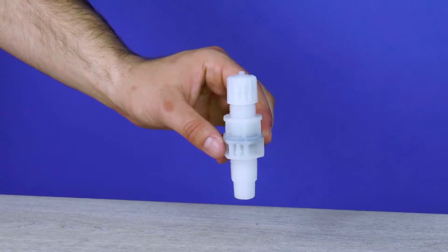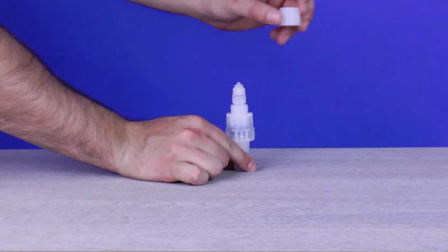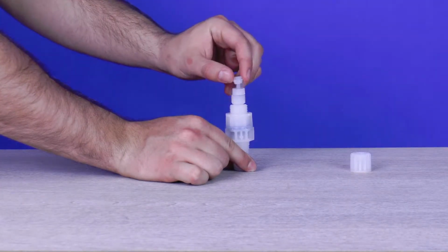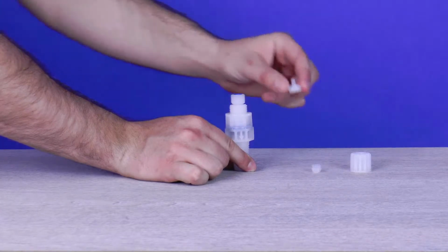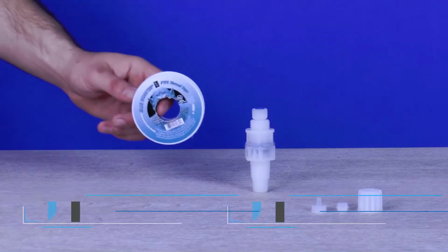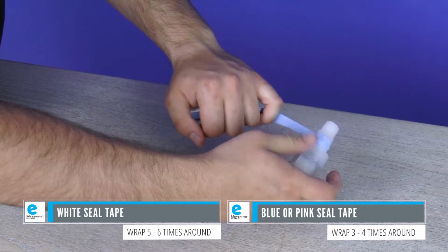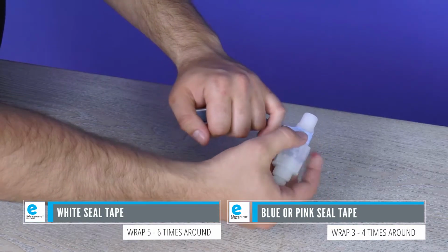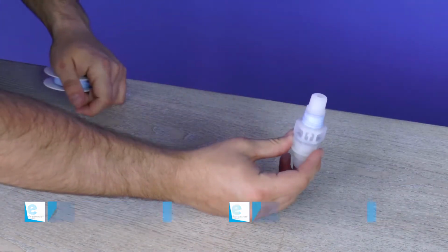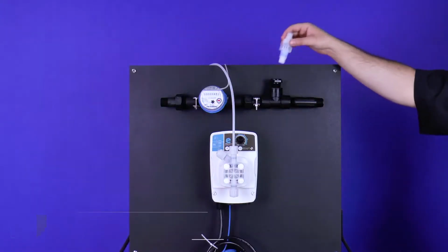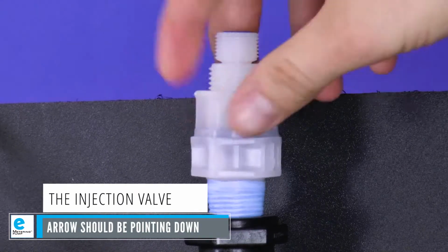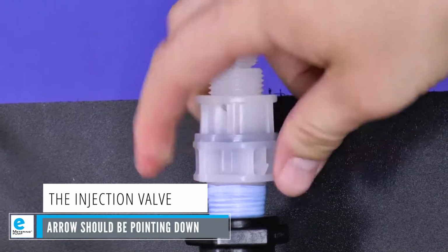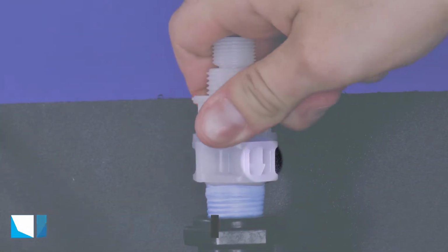Injection valve. To rebuild this section, take the new injection valve out of the tubing kit and remove the tube nut, collar, and nozzle. Set them aside, but make sure not to lose them. Take the thread seal tape and wrap it around the threads of the injection valve for the necessary size, either 3/8 or 1/2 inch. Install and hand tighten the injection valve into the installation saddle or T in the supply line. Once again, do not over-tighten.